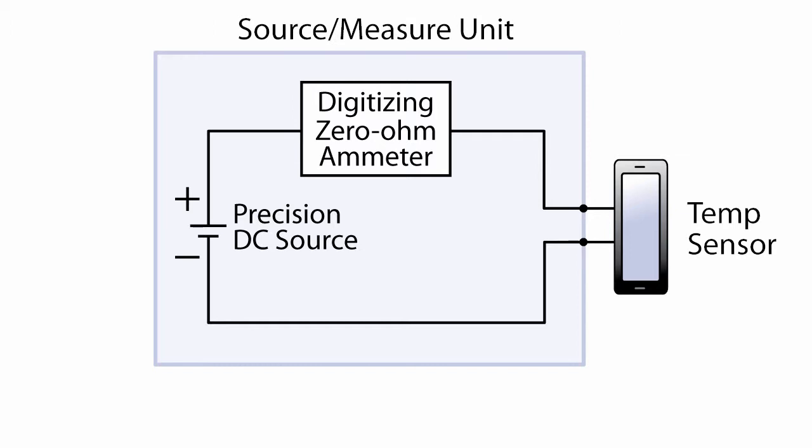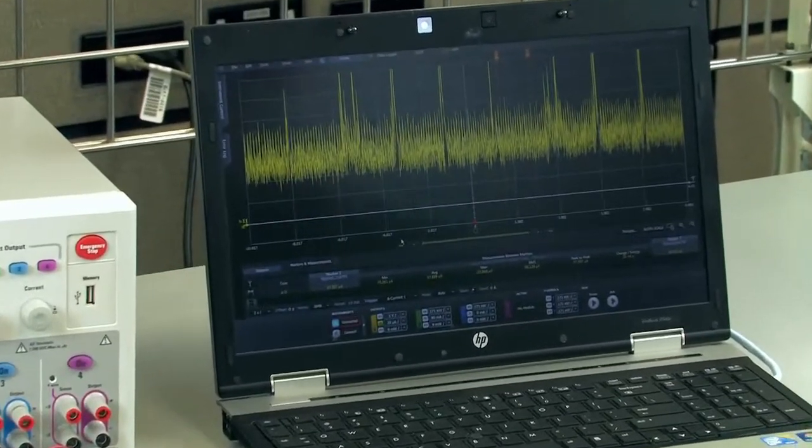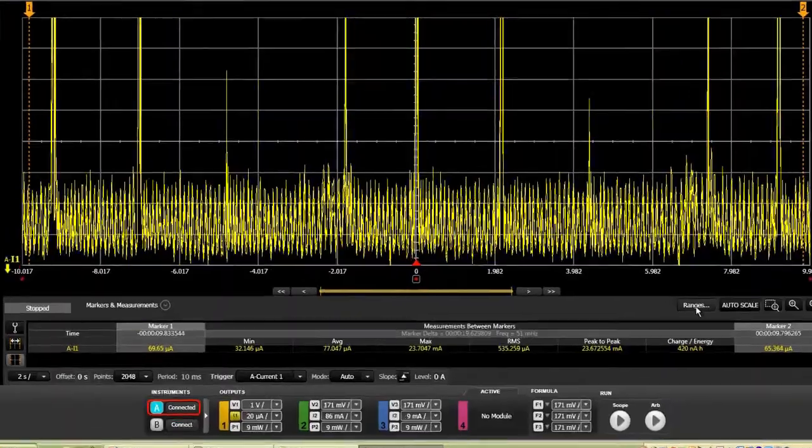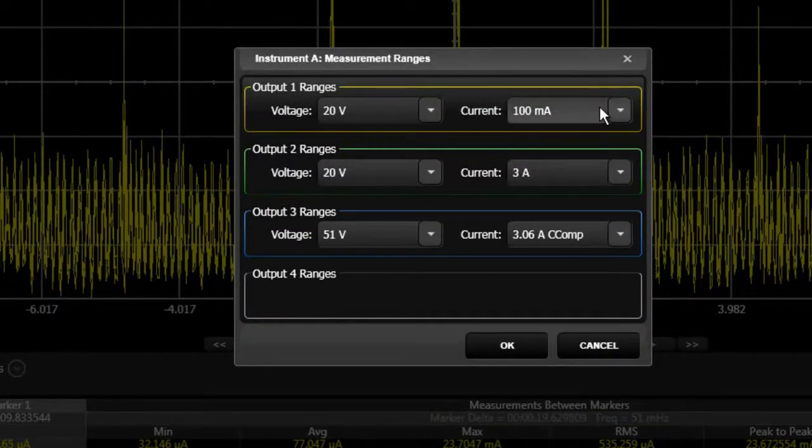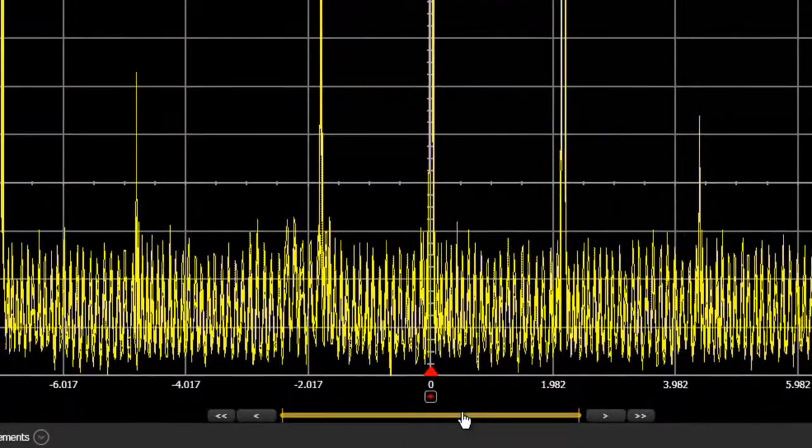Initially, the current was measured with the N6781A set to its fixed 100 mA measurement range. As shown here, this is comparable to the way conventional test equipment would be forced to make this measurement, because of the 21 mA transmit state current pulses.